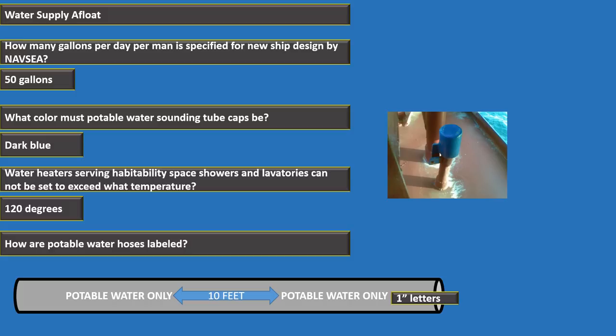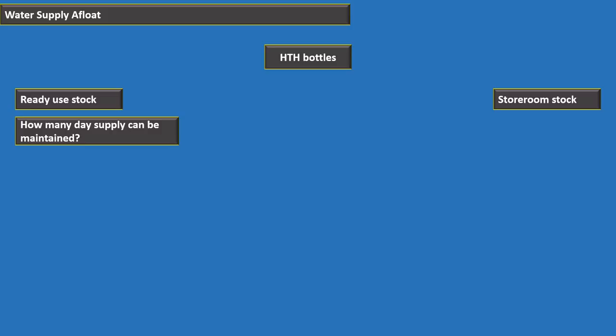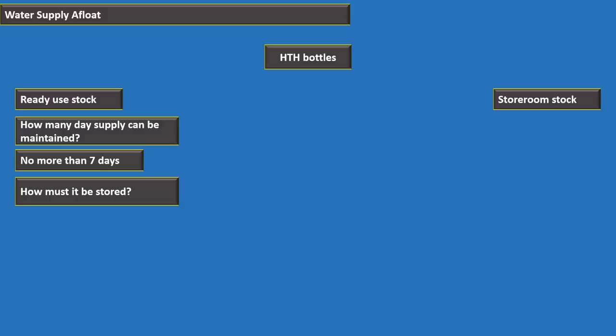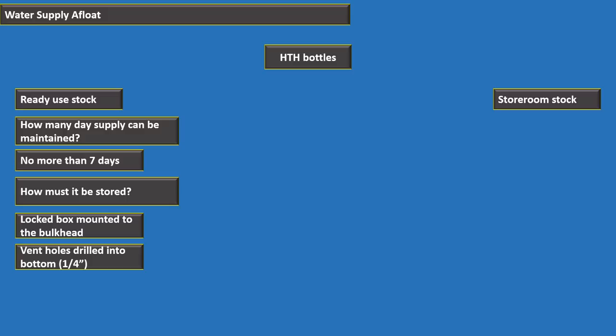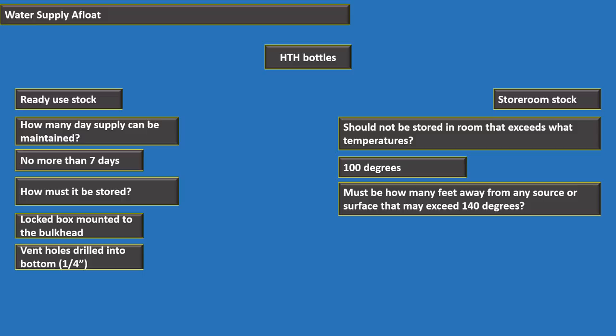For HTH (high-test hypochlorite) bottles: ready-use stock supply cannot exceed seven days. Ready-use stock is stored in locked boxes mounted to the bulkhead with ventilation holes at least one-quarter inch drilled into the bottom. Storeroom stock must be in a room that does not exceed 100 degrees and must be at least five feet away from any surface exceeding 140 degrees.